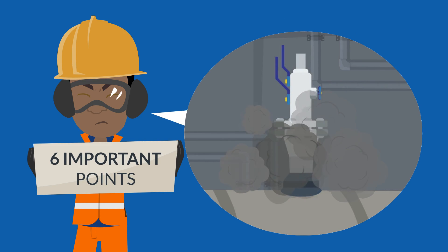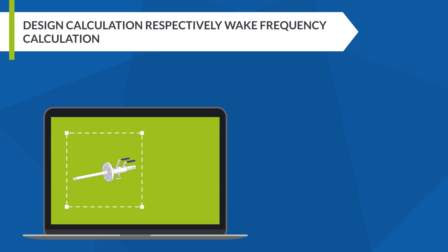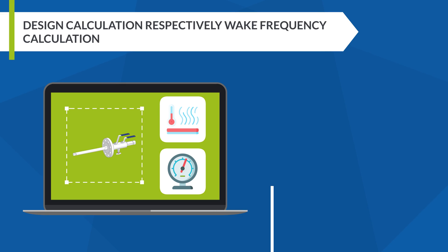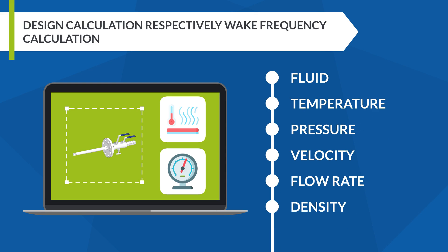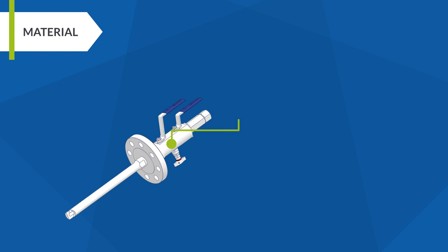Design calculation and wake frequency calculation. Since the design requires thermal and stress considerations, you should consider the necessary process data like fluid temperature, pressure, velocity, flow rate, density, and viscosity. Material: the material grade should be suitable to the service and the type of chemicals to be injected.